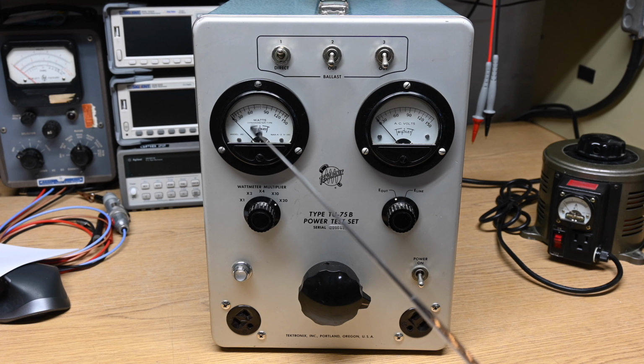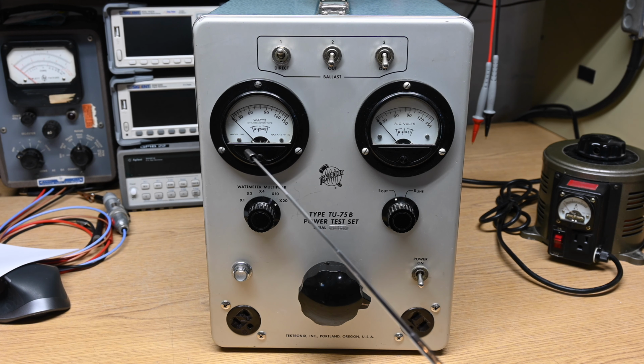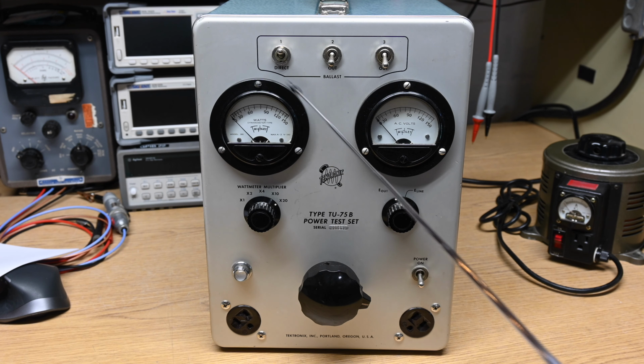Up here we have our watt meter. Now this watt meter actually has 4 connections on the back, 2 for voltage and 2 for current, and it comes up with the reading on the fly. There's a custom transformer scaling that down so that it doesn't exceed the power rating of this, which is 150 watts. So this knob is the watt meter multiplier.